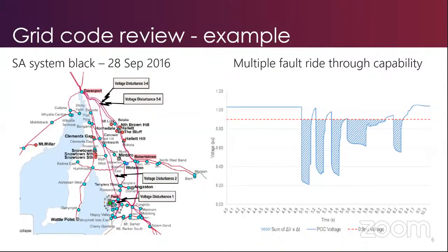It may not be exactly that, but when we look back, experts identified this as a requirement we should cover in our grid codes. To the right, during the 2018 update, multiple fault ride-through capability was introduced. Since that came into effect, when a generator is connecting to the National Electricity Market, they have to do an assessment and provide evidence they can meet this particular requirement.